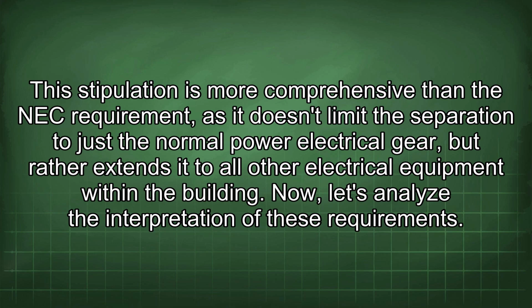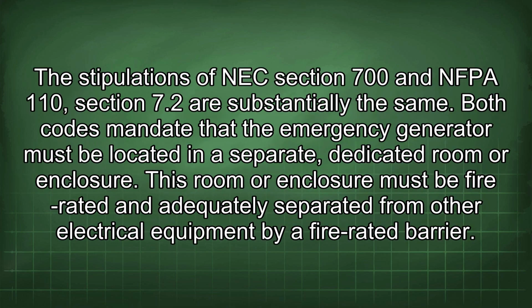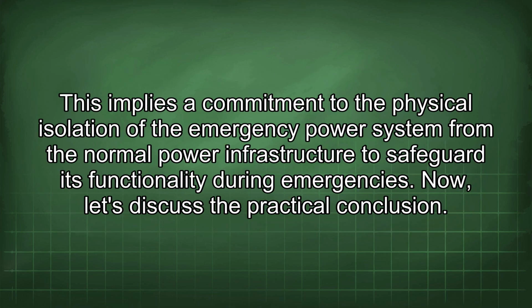Now let's analyze the interpretation of these requirements. The stipulations of NEC Section 700 and NFPA 110 Section 7.2 are substantially the same. Both codes mandate that the emergency generator must be located in a separate, dedicated room or enclosure. This room or enclosure must be fire-rated and adequately separated from other electrical equipment by a fire-rated barrier. This implies a commitment to the physical isolation of the emergency power system from the normal power infrastructure to safeguard its functionality during emergencies. Now let's discuss the practical conclusion.